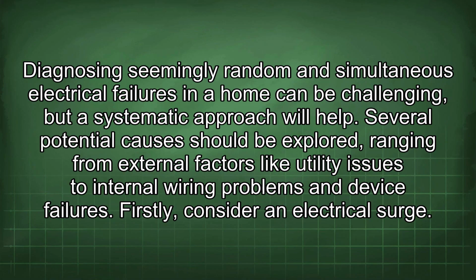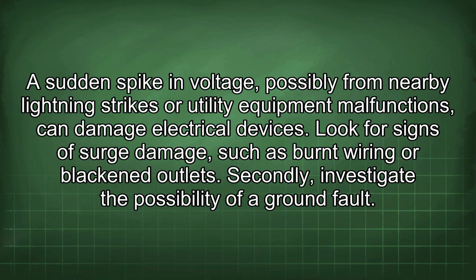Diagnosing seemingly random and simultaneous electrical failures in a home can be challenging, but a systematic approach will help. Several potential causes should be explored, ranging from external factors like utility issues to internal wiring problems and device failures. Firstly, consider an electrical surge. A sudden spike in voltage, possibly from nearby lightning strikes or utility equipment malfunctions, can damage electrical devices. Look for signs of surge damage, such as burnt wiring or blackened outlets.